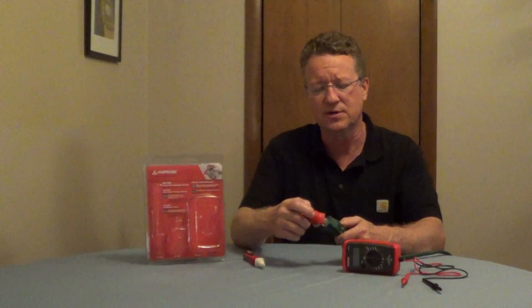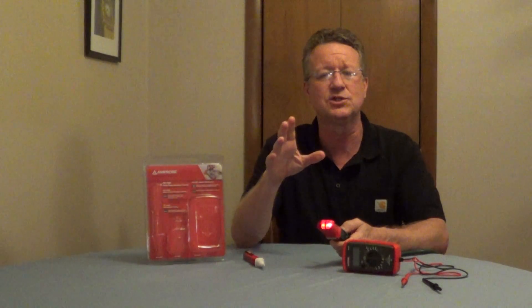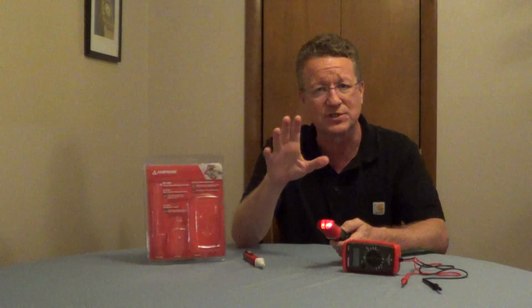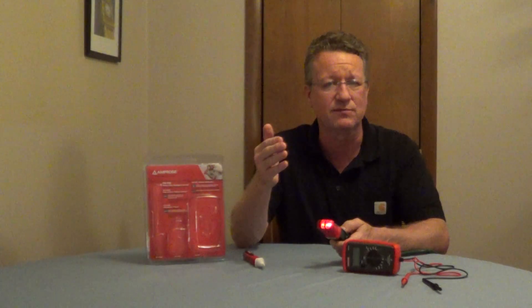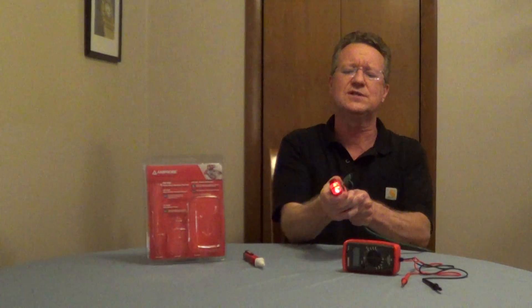The outlet tester is going to let you know whether there's power to an outlet. It's also going to let you know whether it's grounded properly for safety, and also whether it has reverse polarity for safety. This is also going to tell you whether you have an open neutral or an open ground, so it does a variety of tests.